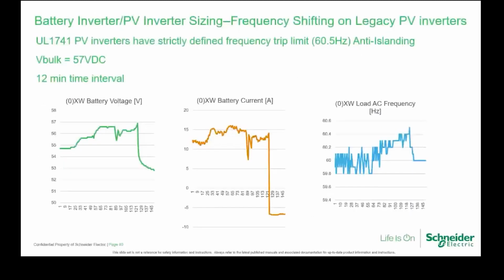So I'm looking at the actual battery voltage. You can see over here on the left-hand side, the battery voltage rises from, say, 54.7 by the looks of it, up to 57 volts for the bulk voltage shift. So you program the XW Plus, and then the battery current would start dropping off. And you can see the frequency would then rise so that it matches what the battery charging requires.